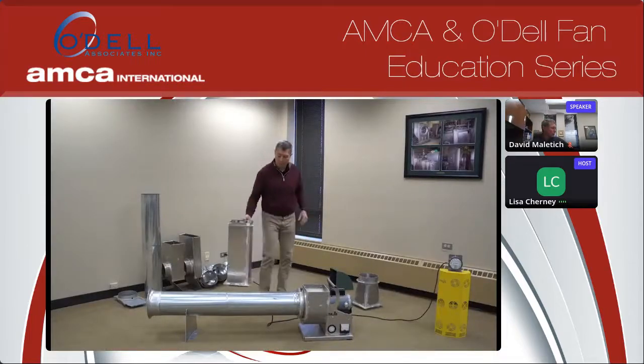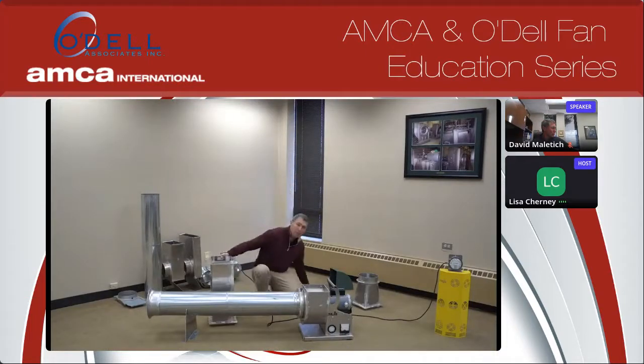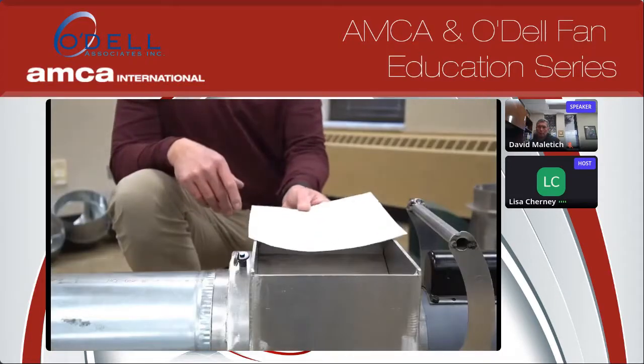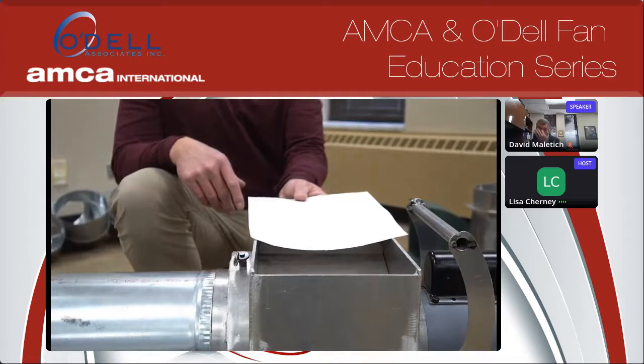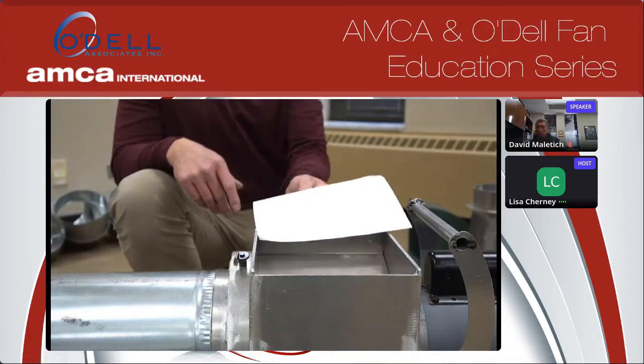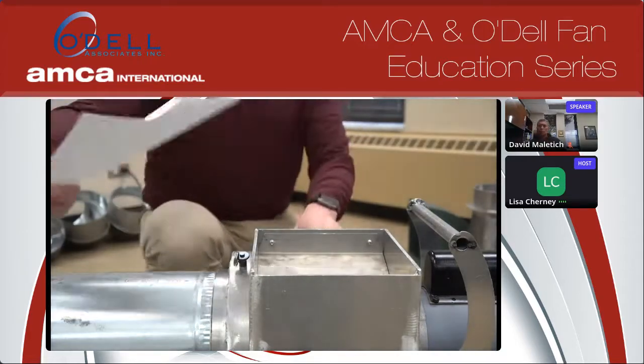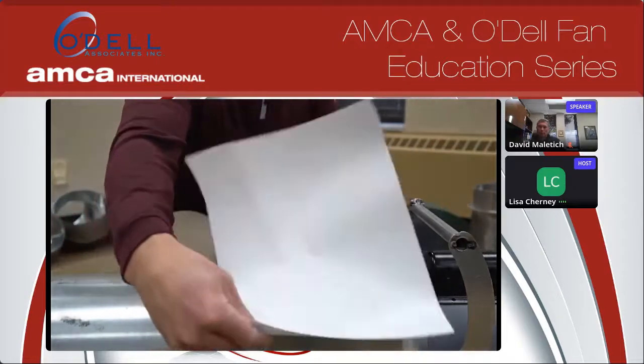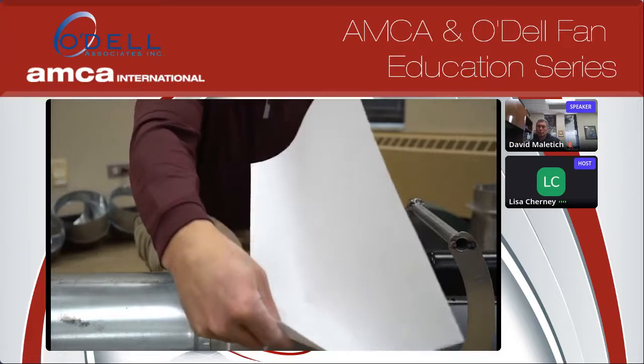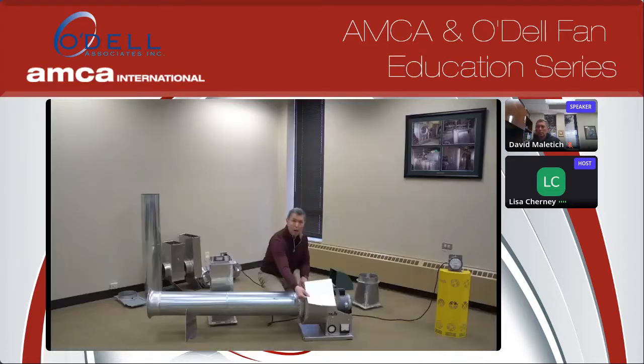And what I mean by velocity profile is when we take this piece of paper here, just a normal 8x11 piece of paper, put it at the discharge of the fan, notice that the air actually is negative pressure here and actually sucks the piece of paper into the fan. And if I put it on the other side of the volute shape, it's positive pressure and it actually blows the piece of paper upward. So as air discharges the fan, it's not laminar across the whole discharge, it's all focused on this section of the fan.